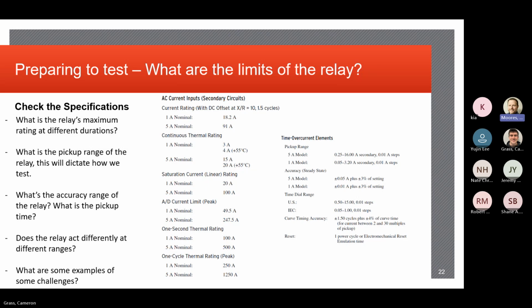That it's monitoring the system and it's going to see the same thing. But you've got to make sure you set your tests up and your test leads so they're capable of carrying that amount of current. You're setting your tests up so that they're only there for a moment, a very, very small period of time, not continuous, because that's what will cause the burnup.